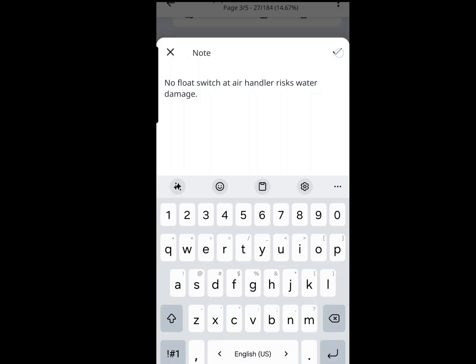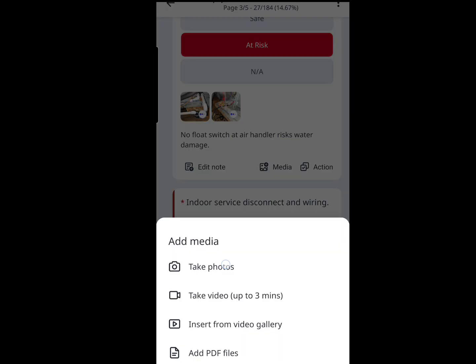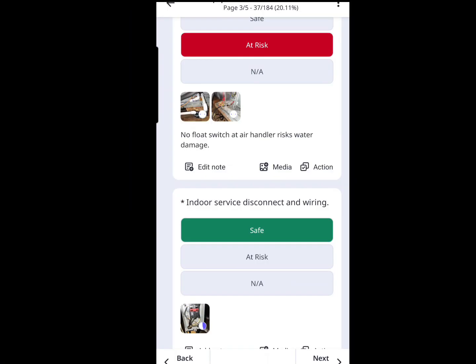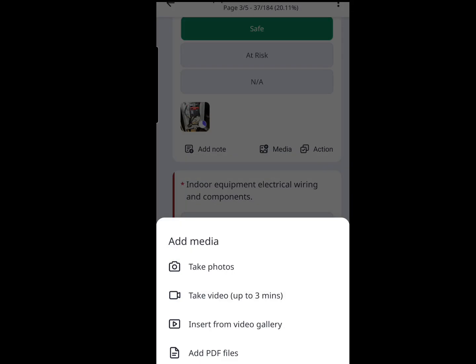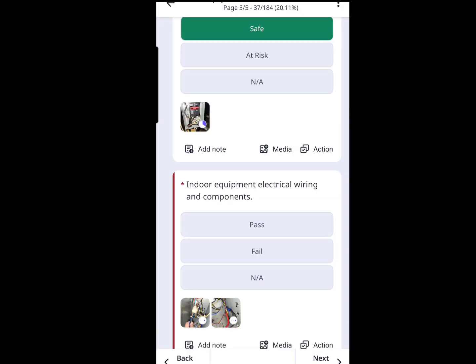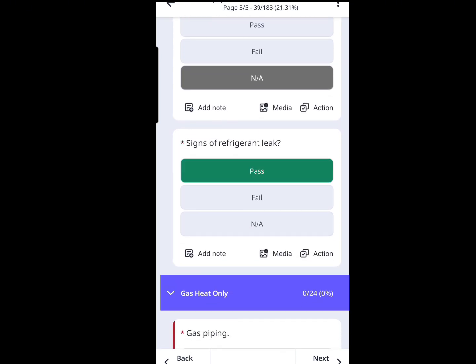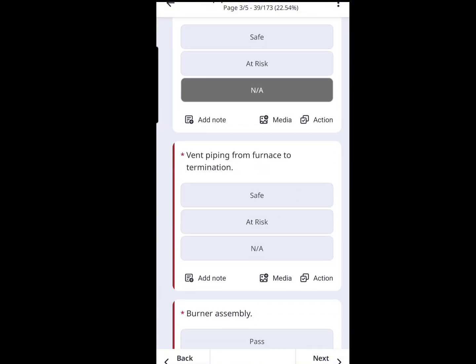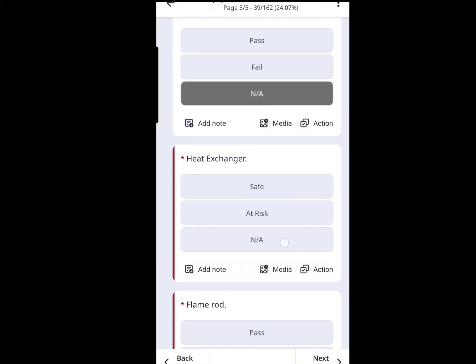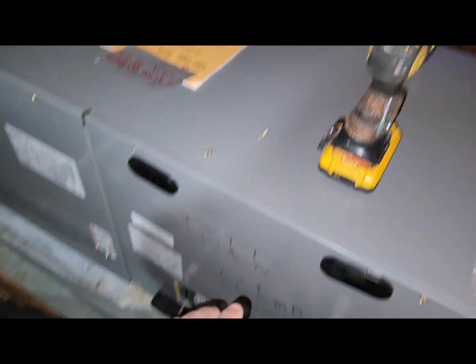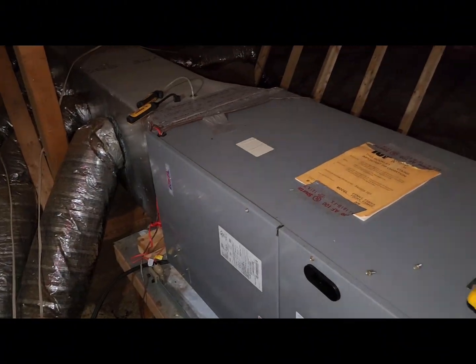We move to the service disconnect. I always check disconnects because I've had a lot of service calls over the years with burnt wires and failing disconnects — so we photo document that. We photo document every element on this unit. We move to the wiring on the indoor unit, making sure we have good solid connections and nothing looks overheated. There's no capacitor because this is an ECM motor, and we don't have any signs of refrigerant leaks. Before going to check the outdoor unit, I go ahead and deploy all my MeasureQuick probes on the inside, then we move to the outside.